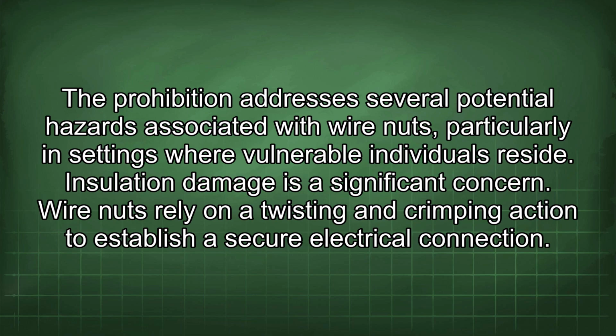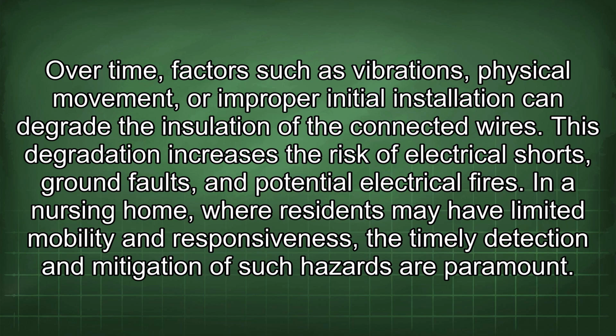Insulation damage is a significant concern. Wire nuts rely on a twisting and crimping action to establish a secure electrical connection. Over time, factors such as vibrations, physical movement, or improper initial installation can degrade the insulation of the connected wires. This degradation increases the risk of electrical shorts, ground faults, and potential electrical fires. In a nursing home, where residents may have limited mobility and responsiveness, the timely detection and mitigation of such hazards are paramount.